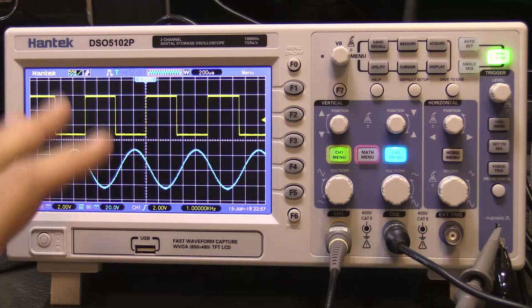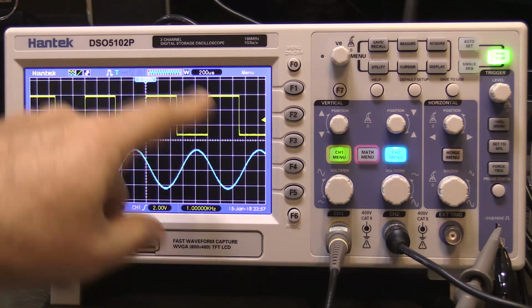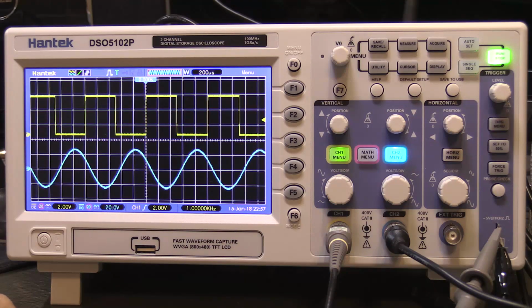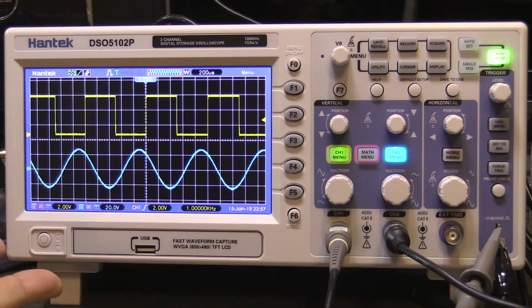You can set it up for more real-time reading or more average reading that brings the noise down. And when you do first turn it on, it'll run you through a calibration procedure. You should calibrate it, and say once a year it'll do a complete calibration, due to component aging and that kind of thing. So it's really got a lot of automation built right into it. And also there is a probe check over here where you can do the probe.